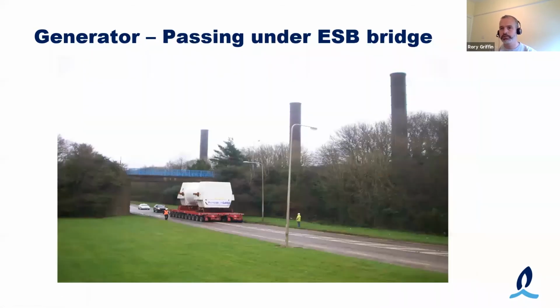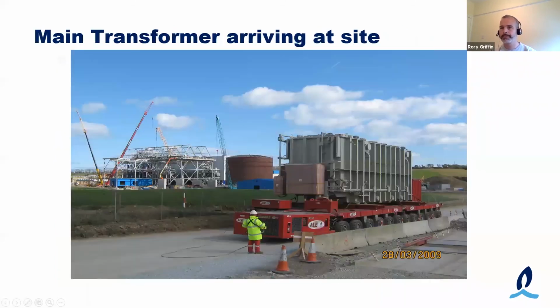This is it coming up the road. In the background, you can see the 3 open cycle units the ESB have at Aghada. This is the main step-up transformer arriving at site. It's a 560 MVA transformer. I suppose there's bigger ones at some of the 400 kV stations, but it's quite a big transformer. Its weight there will be 320 tons, but that isn't full of oil yet. Once it's commissioned and filled with oil, it's a lot heavier. The oil's in there to cool the windings. It's 19 kV up to 220, like we mentioned, but there's also a tap changer on it. So you can control the voltage using the tap changer as well, and also maybe in parallel with the machine.